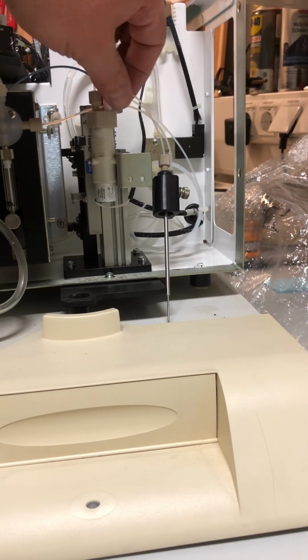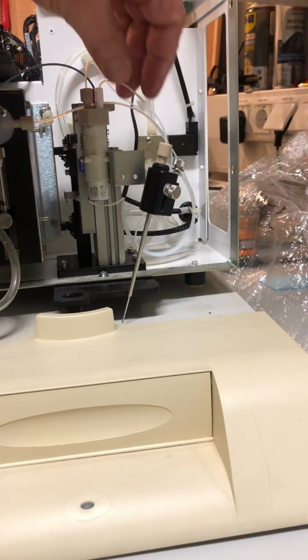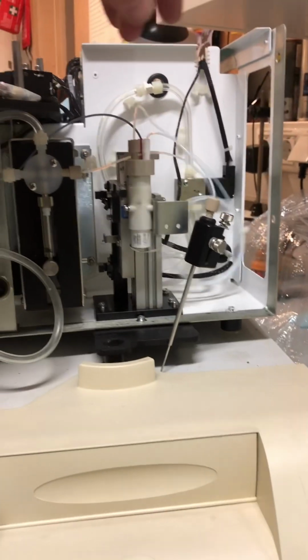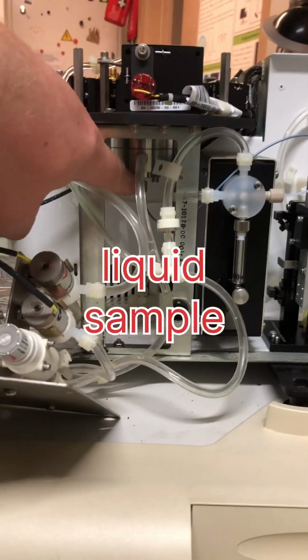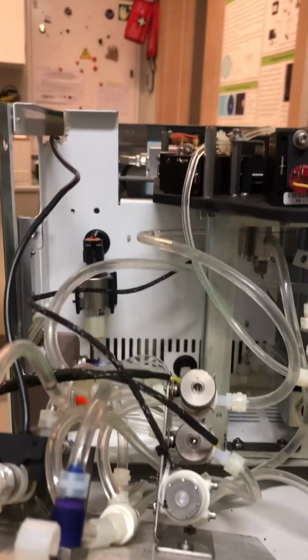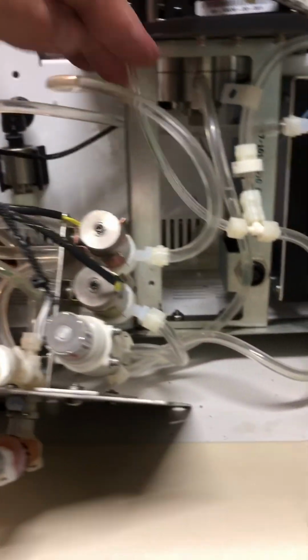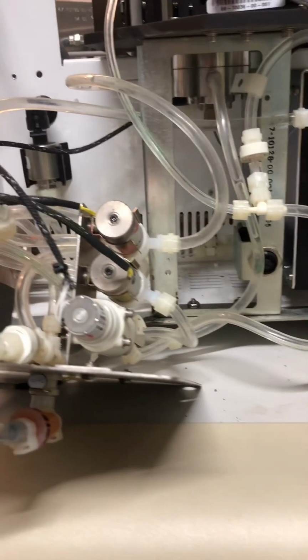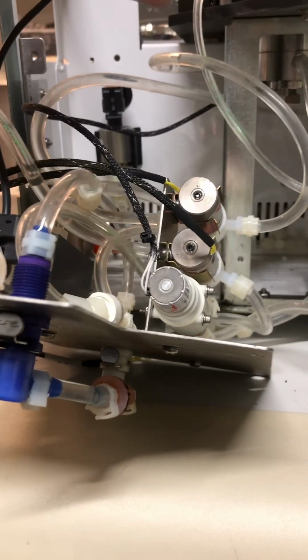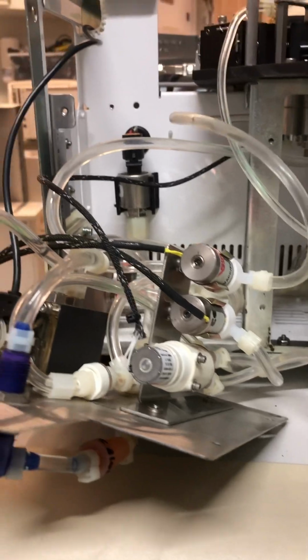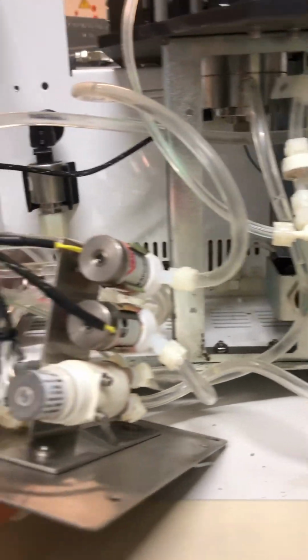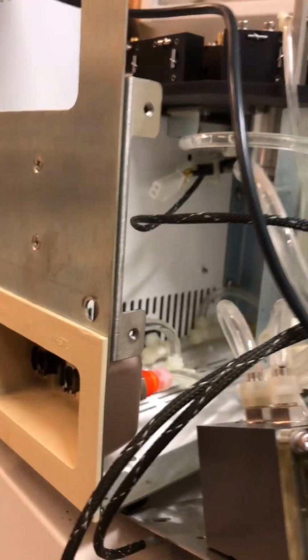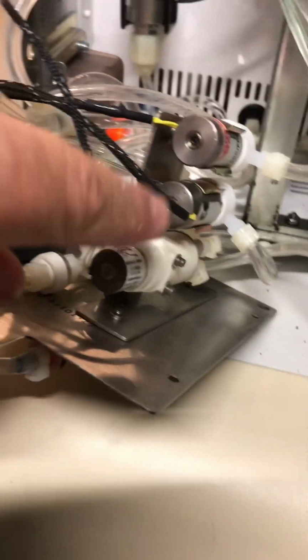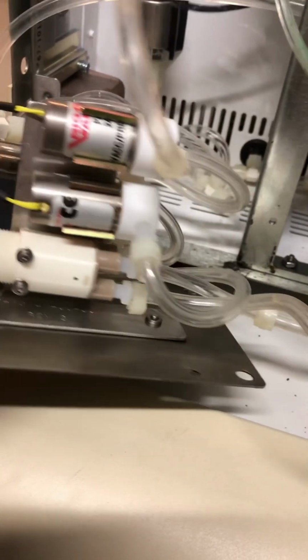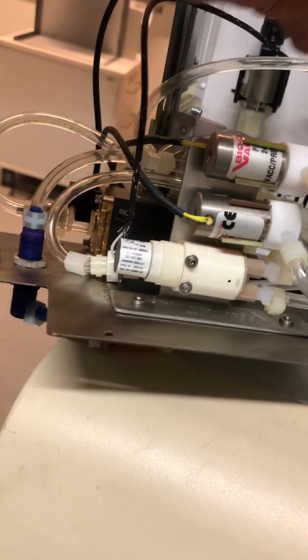three-position switch. Here is this pipette, so I think it's necessary for washing the pipette, and then the signal goes through this blue wire into this module, and there is a capillary which comes out here, and then it is going to waste. This line is waste, also this line is waste. Yeah, so an interesting thing: what is this chemical agent, why is it necessary, and probably there is some clever membrane inside. Is it not the heat exchanger? And then waste goes to a three-way switch on output, and here we have two more relays for this chemical thing.